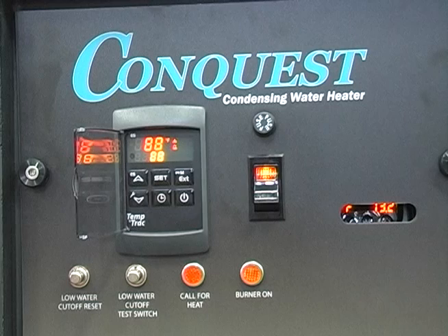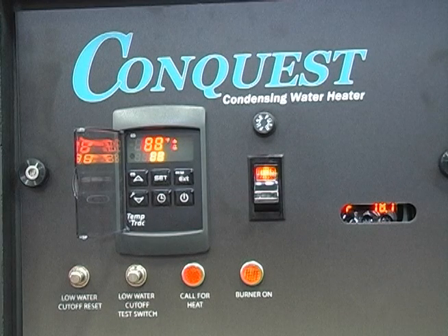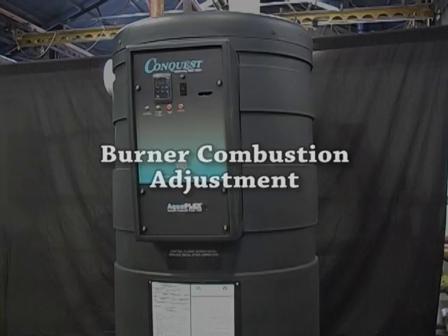If during the test the call for heat panel light does not illuminate, this indicates another safety device may be tripped, which is interrupting the cycle. These devices include the low water cutoff, high temperature limit, or gas pressure switches if equipped. Check the troubleshooting section of the maintenance manual for corrective action.